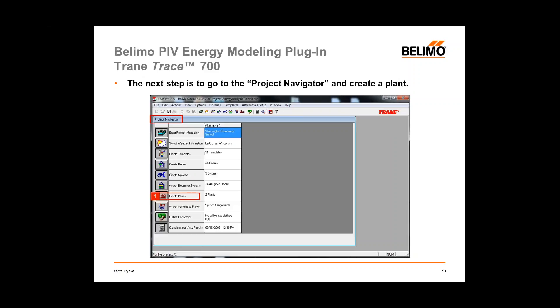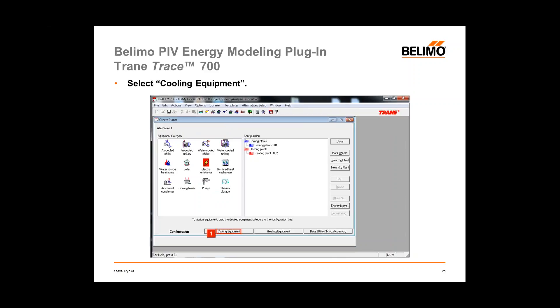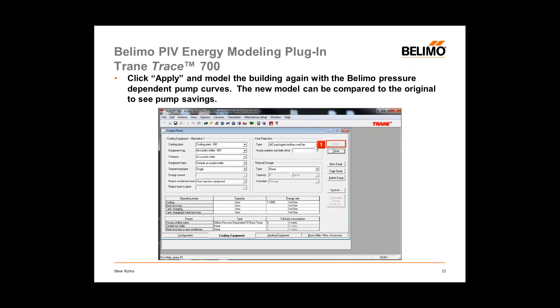Then go to the Project Navigator and select Create Plant. Double-click on Plants and under Create Plants, select Cooling Equipment. Once under the Cooling Equipment tab, select the appropriate Belimo Pressure Dependent Pump. After clicking Apply, the pressure-dependent pump curves are installed. We'll then go back and remodel the building and compare it to the original base model to show the savings associated with pressure-independent valves.